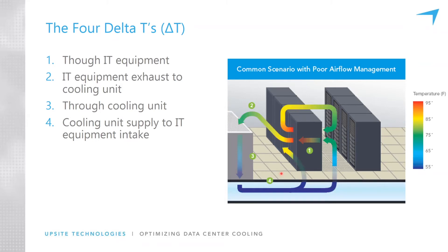However, this is the way facilities actually are. To achieve a maximum intake temperature of 75 or 80 degrees — as most people target — requires, in most environments due to poor airflow management and poor optimization, a supply temperature from cooling units of 55, 60, maybe 65 degrees. That 60-degree air often warms up 20 degrees by the time it reaches the warmest intake temperature, so delta T4 is 20 degrees — a 20-degree increase from the time it leaves the cooling unit to the warmest intake.